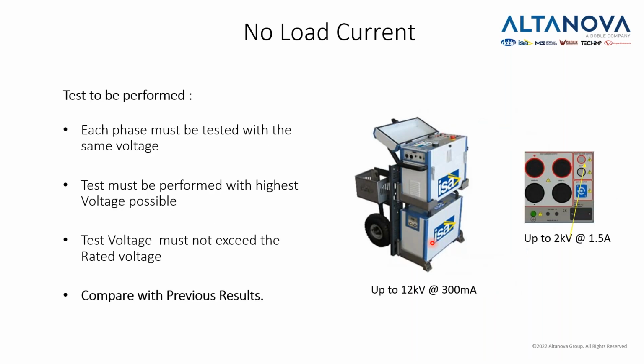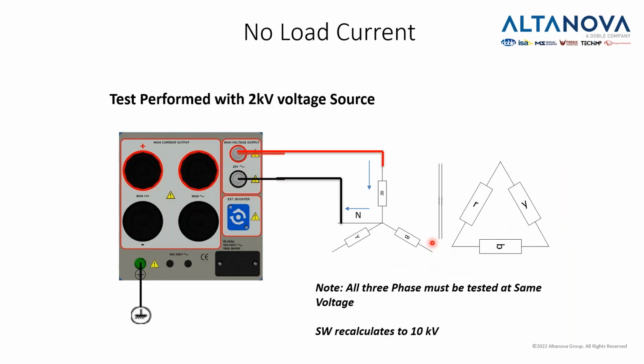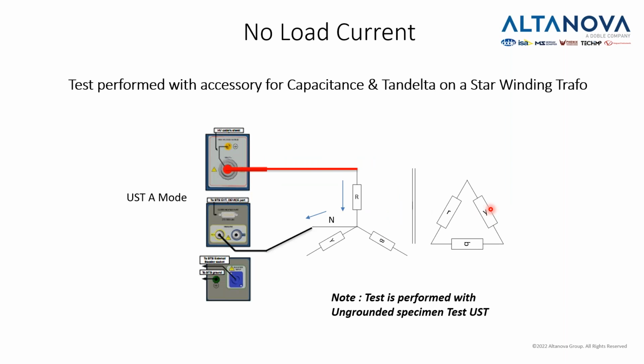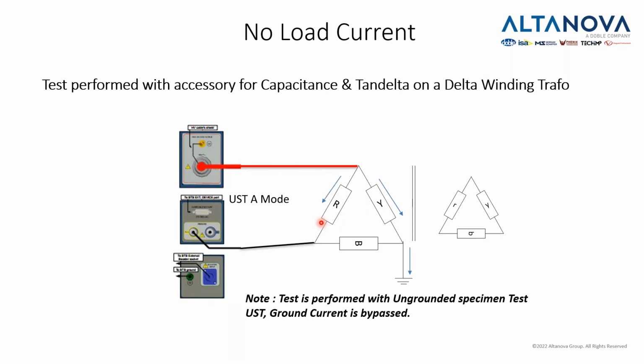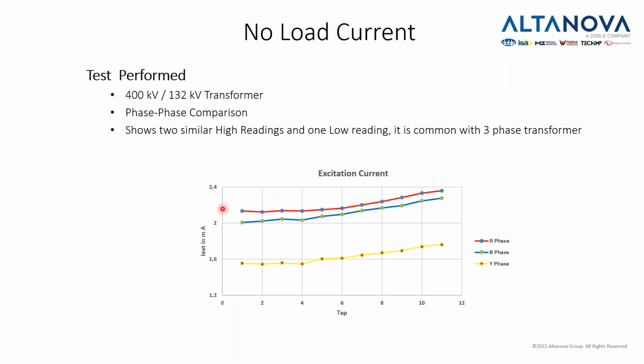Also, the way we should evaluate the results, before evaluation, this is how we do the execution of the test. We connect the primary side with the secondary side open, and we generate the highest possible voltage. Usually, if we cannot generate up to 10 kilovolts, then we need to recalculate, and our devices can do that. What is important is the evaluation of the result. Usually, the middle phase will have lower values because it's in the middle. It has lower losses in comparison to phases A and C, which are on the sides, at the beginning and at the end of the transformer, and have higher losses.